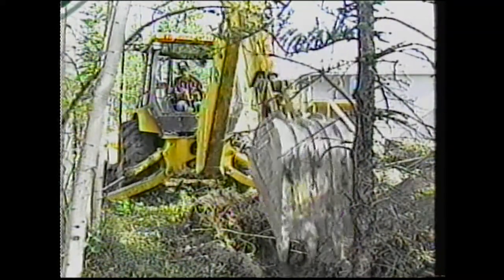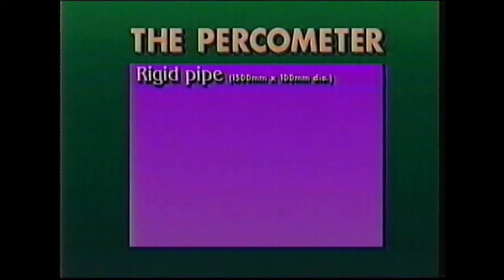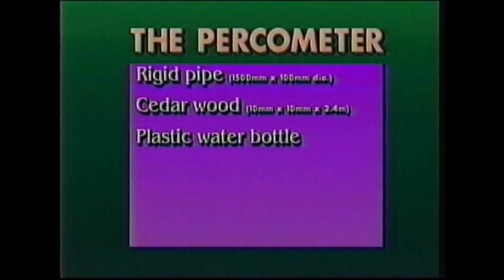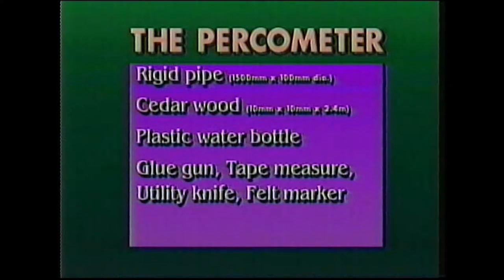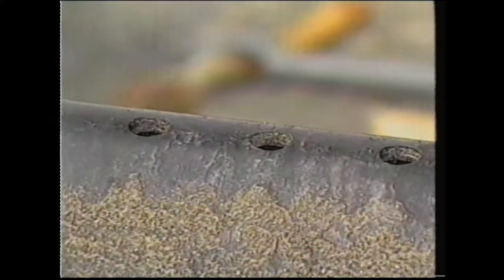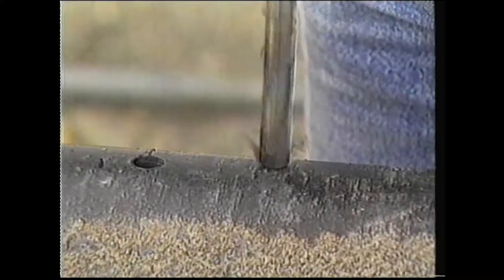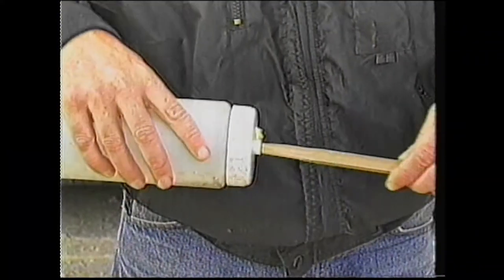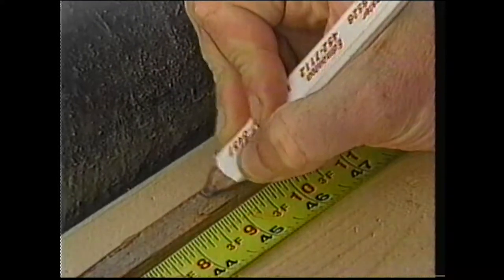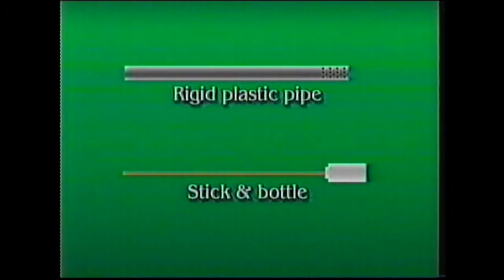The PERC rate can be determined by building a simple percometer using the following materials: one 1500 millimeter length of rigid plastic pipe, 100 millimeters in diameter; one piece of 10 millimeter by 10 millimeter by 2.4 meter cedar wood strip or 1.5 to 3 millimeters diameter of stiff wire; one plastic water bottle with watertight lid; hot glue gun, measuring tape, utility knife and fine-tipped felt marker; and drill and 13 millimeter drill bits. Begin by drilling six rows of holes in the bottom 300 millimeters of the pipe. Using the utility knife, cut a small X dead center on the lid of the water bottle and insert the wood strip or wire into the X until it touches the bottom of the bottle. Hot glue the area where the wood enters the bottle lid and let it harden. Measure and mark five millimeter increments on the top one meter of the wood strip. You have your percometer.